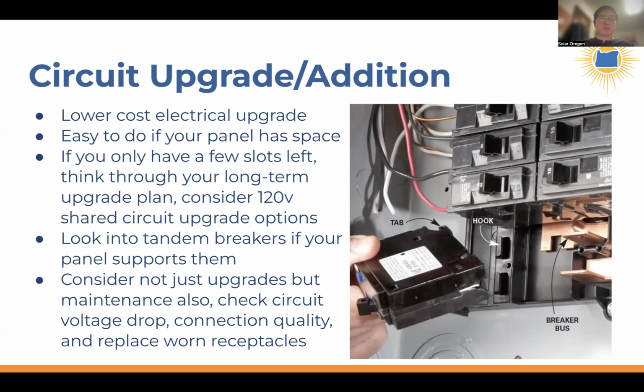One thing that's come into play: bigger appliances that traditionally use a two-pole, two-slot 240-volt circuit breaker now have 120-volt shared circuit options. Some of these are water heaters, some are even heat pumps. Think strategically about those options and compare them with having an electrician pull a new 240-volt circuit and using those slots.